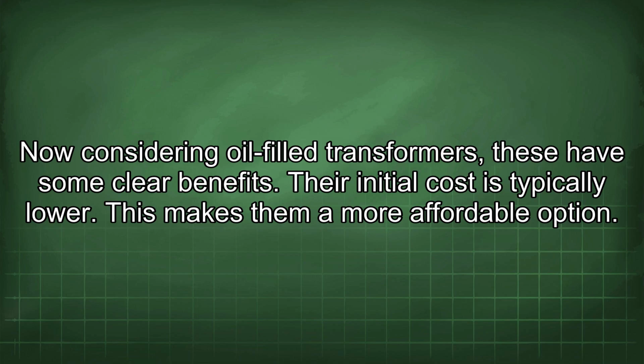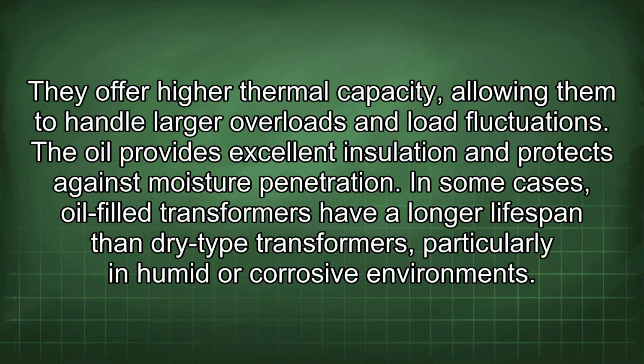Their initial cost is typically lower. This makes them a more affordable option. They offer higher thermal capacity, allowing them to handle larger overloads and load fluctuations. The oil provides excellent insulation and protects against moisture penetration. In some cases, oil-filled transformers have a longer lifespan than dry-type transformers, particularly in humid or corrosive environments.